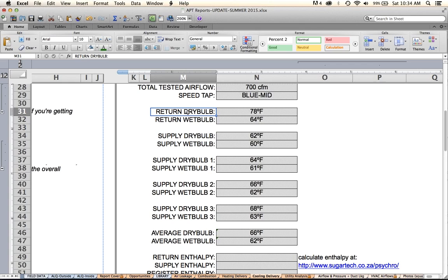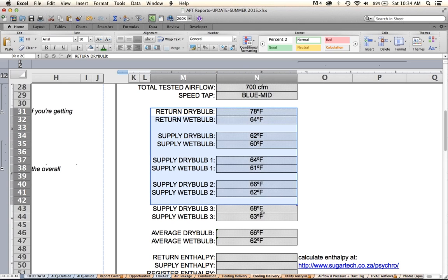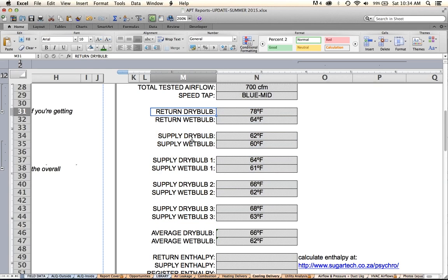Then what we're going to do, and this is a mad dash, this whole thing that we're going to do right here. So we're going to take the return and the supply, dry bulb, wet bulb. Then we're going to run like crazy to a selection of 3 distant registers in the system. And we're going to measure the dry bulb, wet bulb at each of those. And remember that your thermometer is going to take about 30 seconds to kind of equalize here. So you're going to have to literally haul ass to get to these places.